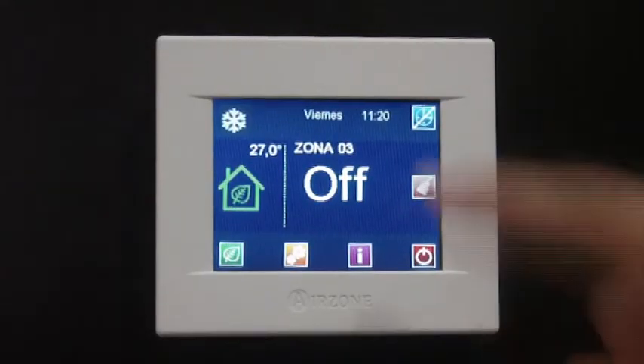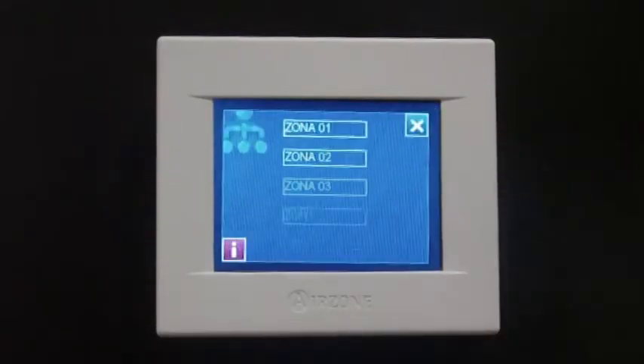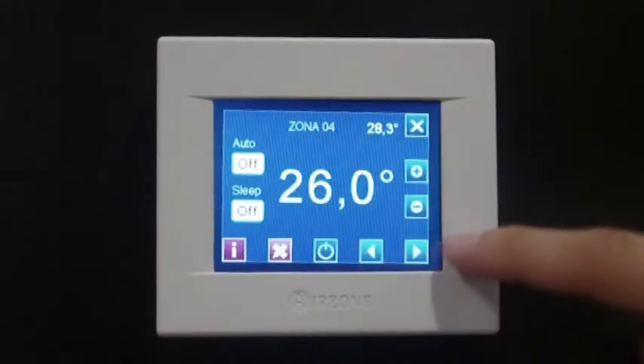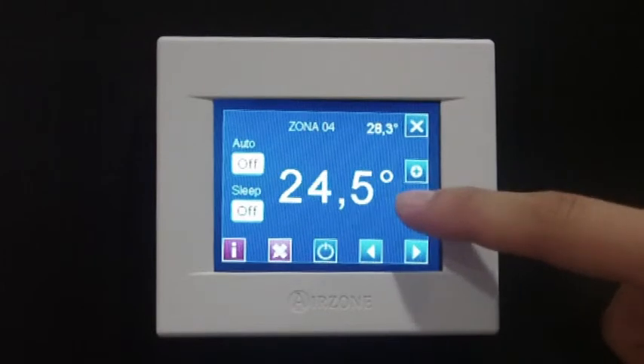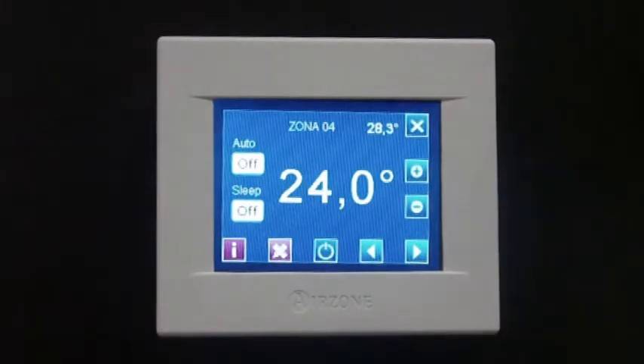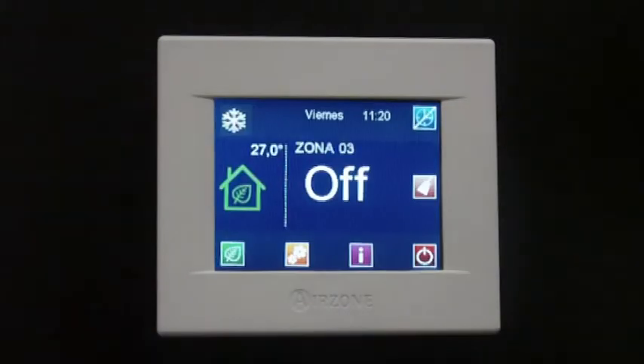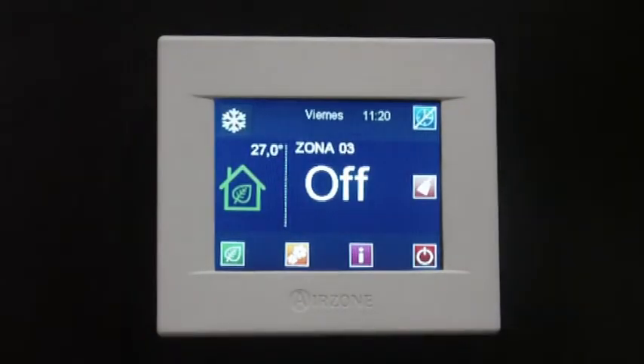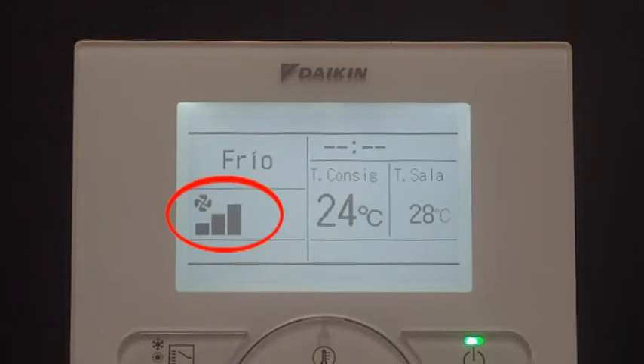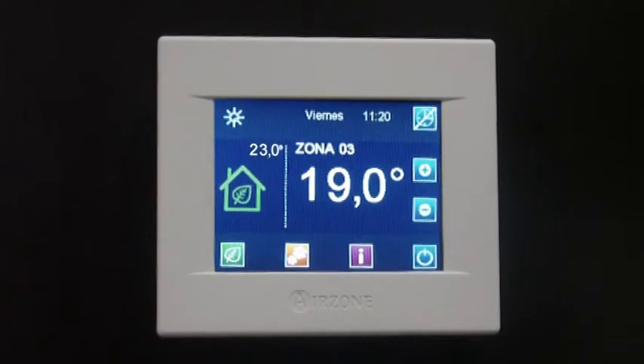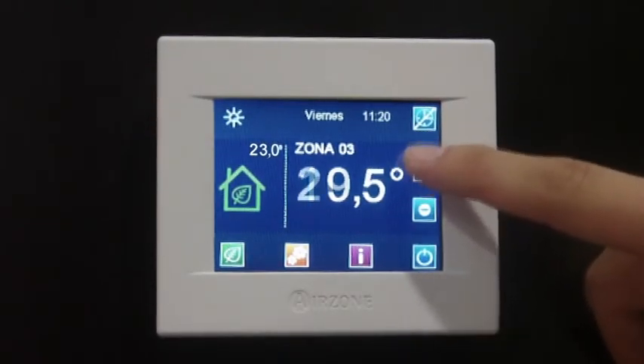Airzone communication gateway also sets the indoor unit fan speed so that the performance of the system is adjusted according to the dynamic behavior of the installation. Hence, when there is one zone in demand, the system will set the indoor unit fan speed to the minimum available. If the number of zones on demand increases, the indoor unit fan speed will increase accordingly.